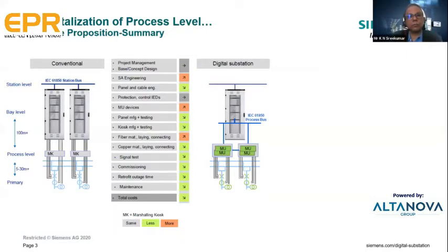If you look briefly at the value proposition, starting from the left bottom with the primary part of the substation and moving up to process level, typically you use a lot of copper cable for point-to-point connections from CTs and VTs to the marshalling kiosk. Distances depend on substation design, but could be in the range of 5 to 30 meters plus.